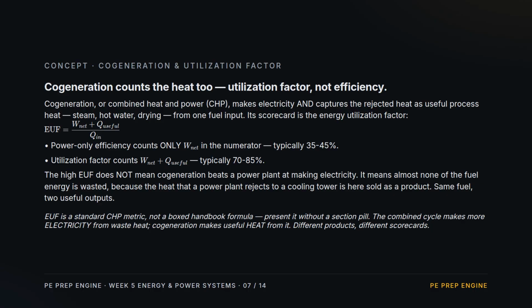Cogeneration, also called combined heat and power, makes electricity and then captures the rejected heat as a useful product. Process steam, hot water, drying, all from one fuel input. Its scorecard is the energy utilization factor, net power plus useful heat, over fuel in. A power-only efficiency counts just the electricity, typically 35 to 45%. The utilization factor counts power plus heat and runs 70 to 85%. But that high number does not mean cogeneration is better at making electricity. It means almost no fuel energy is wasted, because the heat a normal plant dumps to a cooling tower is here sold as a product. Same fuel, two useful outputs. Like the combined cycle formula, EUF is a standard metric you bring yourself, not a boxed handbook equation.